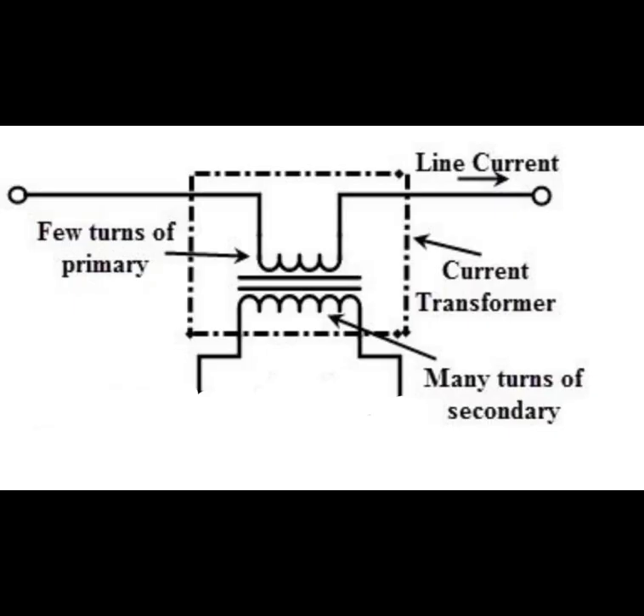At this point, the open-circuited secondary of a current transformer can generate dangerously high voltages, potentially reaching thousands of volts. This occurs because the magnetic flux in the core continues to increase as there is no load across the secondary circuit. In summary, the basic thing to know is that as current is stepping down, voltage is stepping up simultaneously in current transformers. Because of this increase in voltage, current transformer secondary circuits should not be left open.